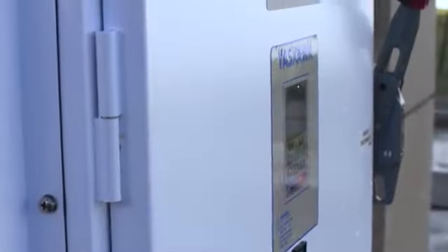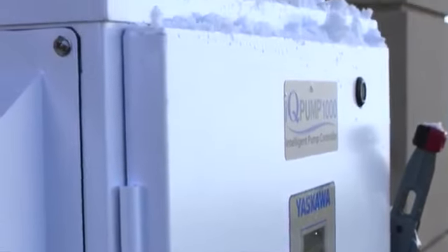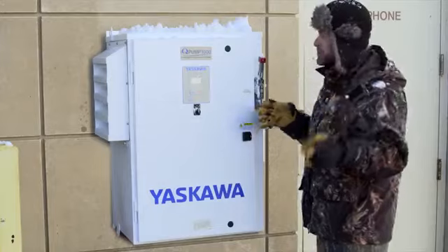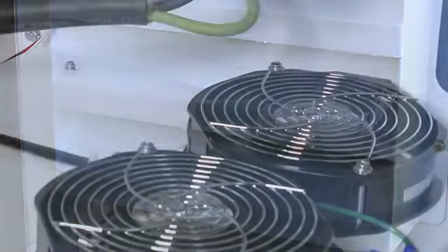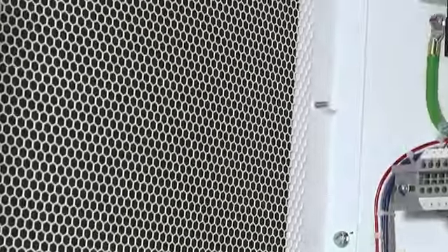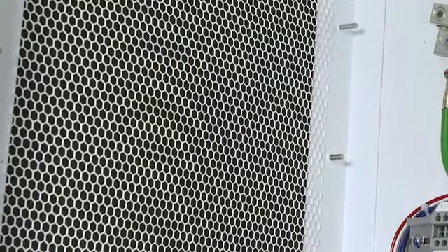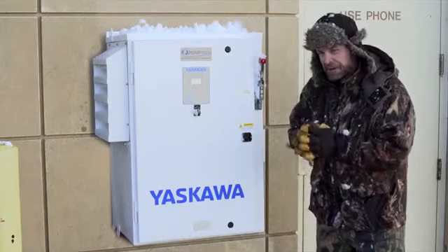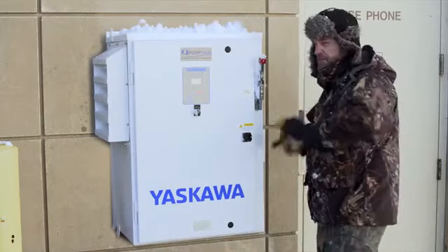They provide protection against falling rain, sleet, snowballs, and prevent corrosion from the formation of ice on the enclosure. Rain hoods over the ventilation holes prevent rain and insects from entering the cabinet. Yaskawa 3R enclosures also include filters to provide some protection against the ingress of dust and dirt, which is not a requirement for UL or NEMA specifications.